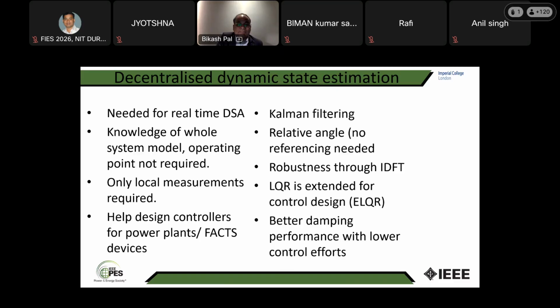This is needed for real-time DSA. Knowledge of the whole system model and operating point are not required. Only local measurements are required. It helps design controllers for power plants and FACTS devices. What is the process we applied? Kalman filtering. We have used the unscented Kalman filtering by sigma point generation, not extended Kalman filtering, because that requires the Jacobian and linearization. Relative angle, no referencing is needed. We have achieved the robustness through IDFT, that is, interpolated discrete Fourier transform.